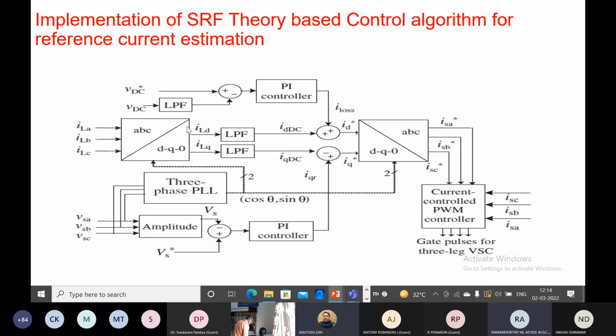What we want to know is the real and reactive power demand of the load. That's why we convert into two decoupled components, ILD and ILQ, using low pass filtering with about 10 to 20 radian per second cutoff frequency, so that any fluctuations or interharmonic components are filtered out. You get a pure active DC component and a pure reactive DC component, meaning straight line components.